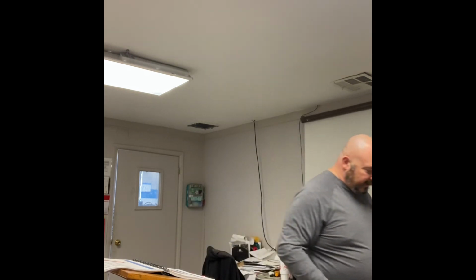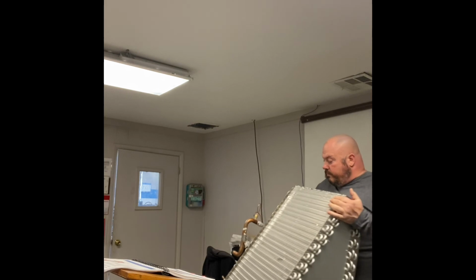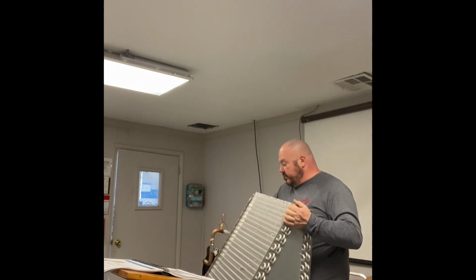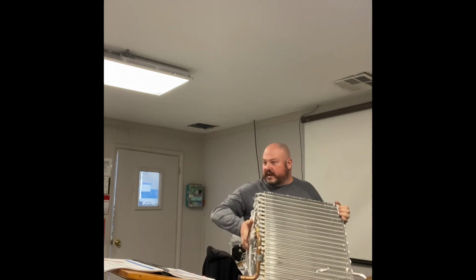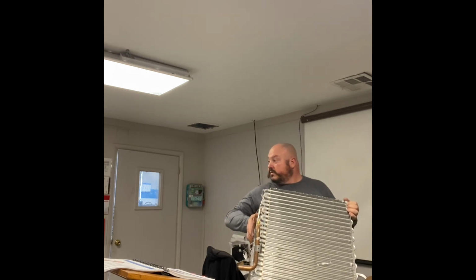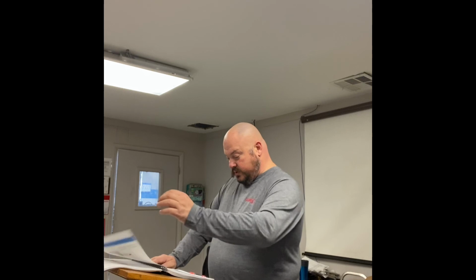Understand? So what we're looking at is on here, our bulb is in the upright position with the device coming off the top of it, and it's after it's left the entire operation. Okay? If you want to get a closer look, you're more than welcome to come up in just a minute and take a look at it. You're going to be using oil traps a lot of times in refrigeration. You need to know where to put it in association with the oil trap. It depends, okay? Depends on your application, what you're going to do, how you're going to do it, okay? Everything else is just talking about having a full column liquid, how it operates.